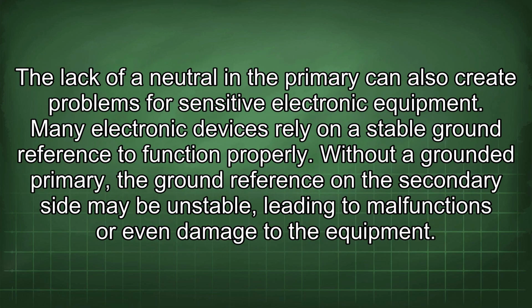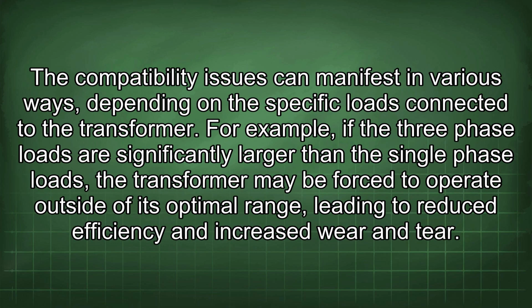The lack of a neutral in the primary can also create problems for sensitive electronic equipment. Many electronic devices rely on a stable ground reference to function properly. Without a grounded primary, the ground reference on the secondary side may be unstable, leading to malfunctions or even damage to the equipment. The compatibility issues can manifest in various ways depending on the specific loads connected to the transformer.